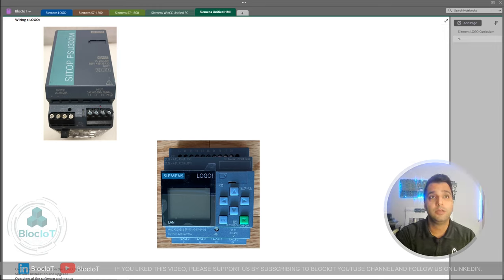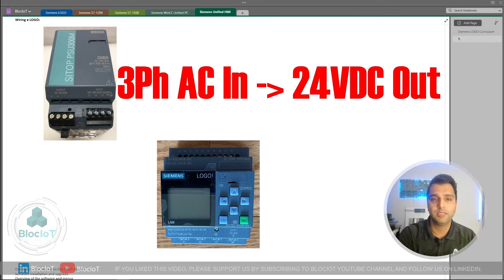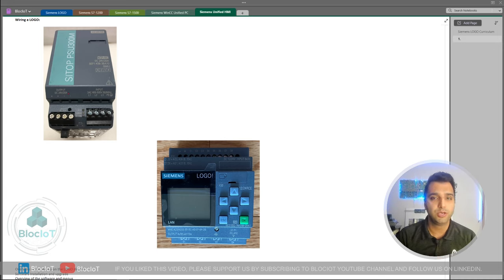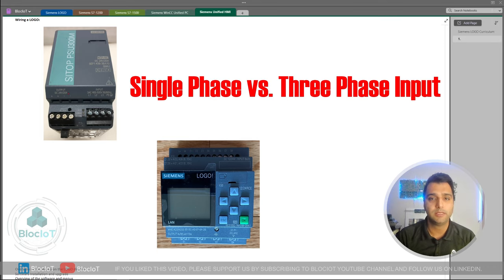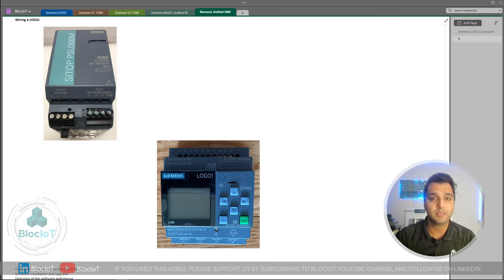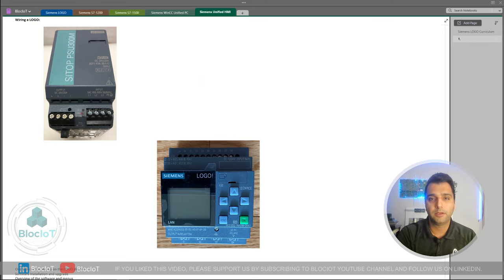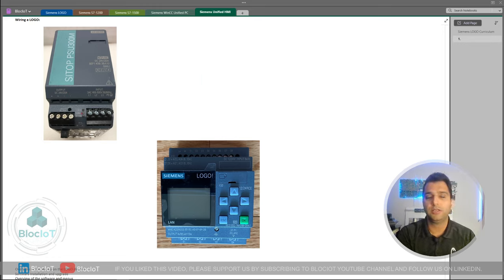This particular power supply is three-phase, meaning the input needs three-phase voltage to convert three-phase AC input to a 24-volt DC output. There are two main parameters to consider when selecting a power supply: first, what is the input type — single-phase, three-phase, or high-voltage DC — and second, what is the output voltage and current. In industrial automation, you mostly deal with 24-volt DC, so the power supply here gives us 24-volt DC with a maximum output current of 20 amps.